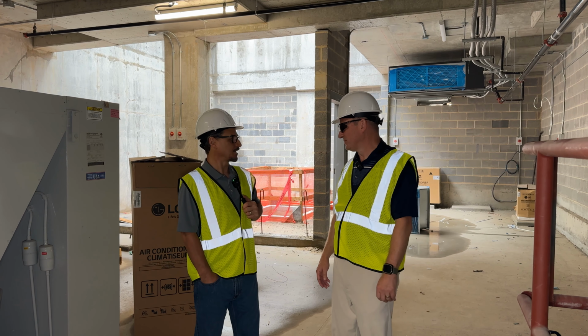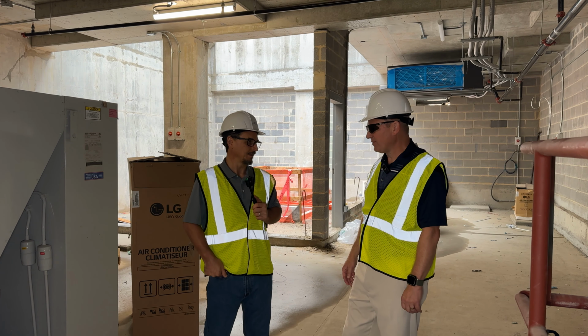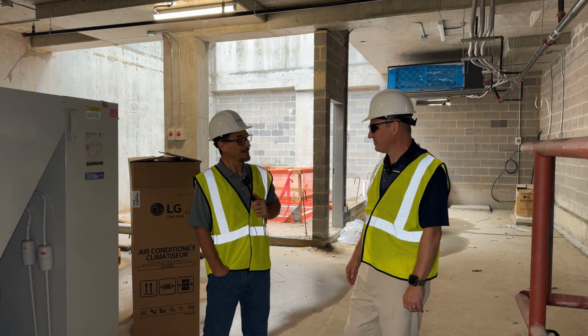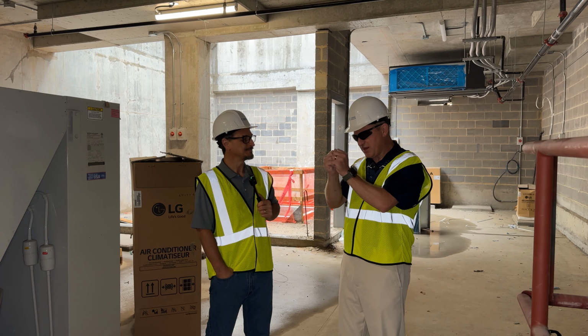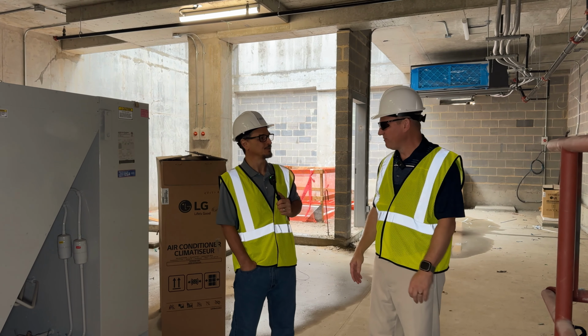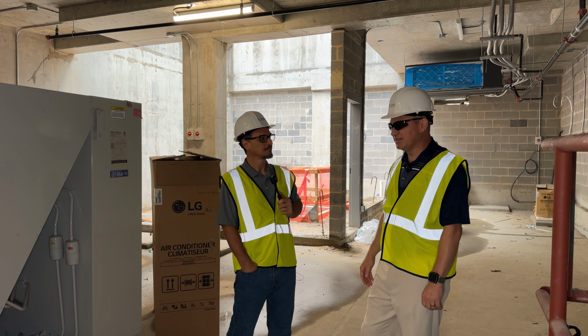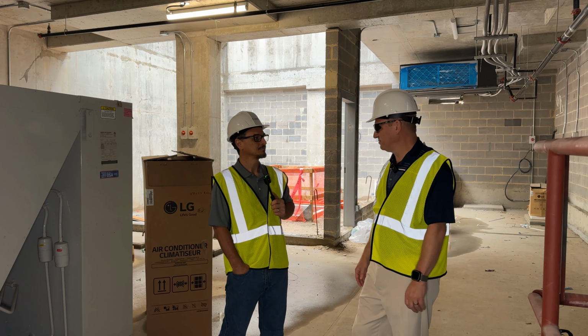And while we're talking about locations of equipment, line lengths, Brett was talking about line lengths a minute ago, the importance of it. I always like them, the closer the better. Absolutely. I always talk about efficiency: if they're right together, then the further apart you get, the less efficient. So we always want them as close. At 150, 200 feet, you've got to really pay attention, and then we definitely have a different issue. So we want to stay within that 75 feet or less if we can. Right. But then obviously we always push that limit.